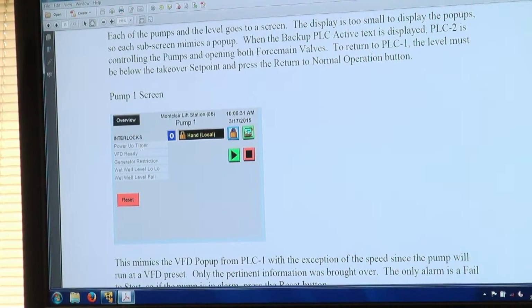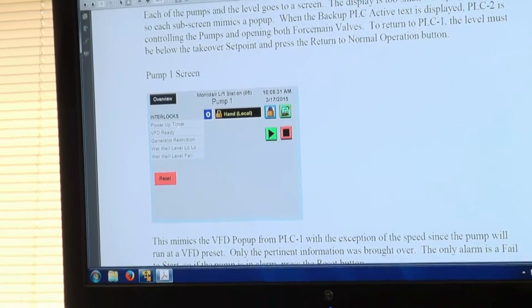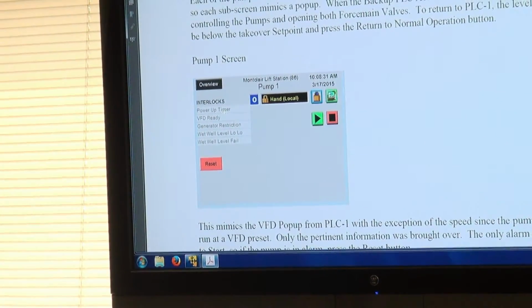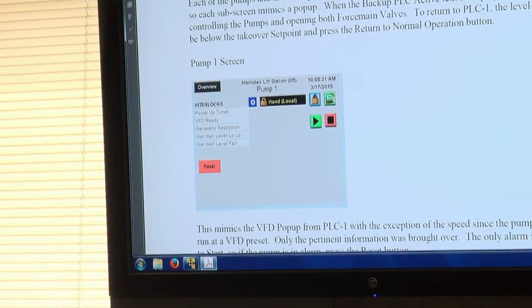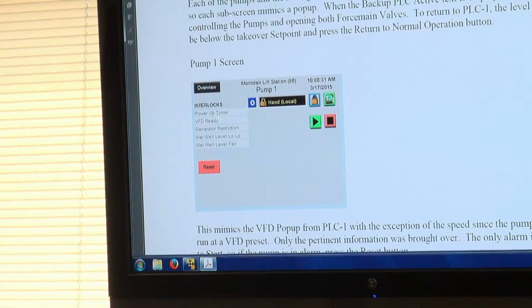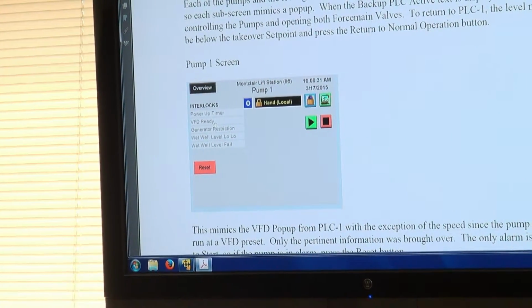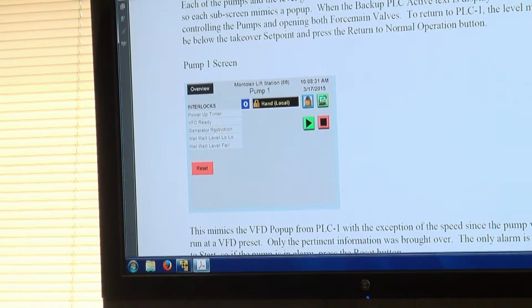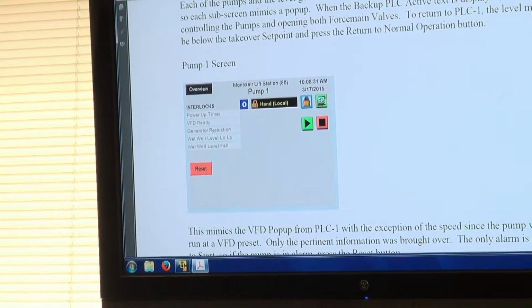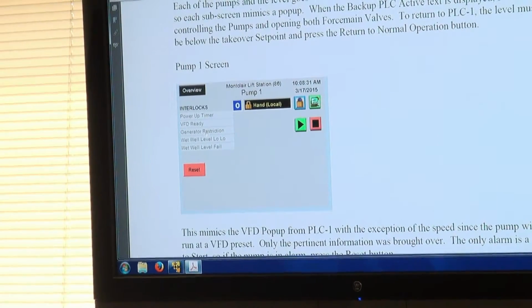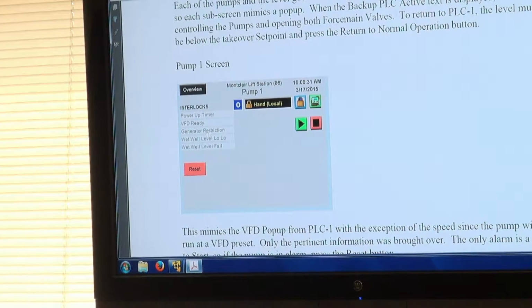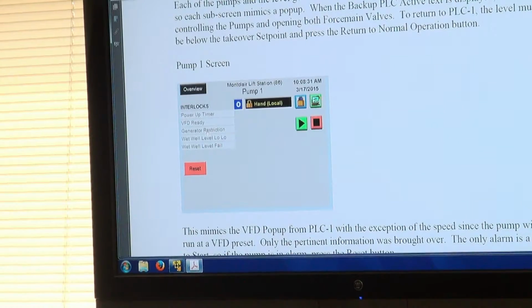We have our power up timer. Basically when a PLC restarts or we switch from emergency to normal or normal to emergency, there's a small delay to make sure that the levels are coming in accurately. We have the ready signal coming in. We have a generator restriction. We talked about that. If 2 pumps are running, it doesn't matter if the VFD's on in hand and running or if it's called from the PLC. If 2 of them are running, the 3rd one will be not ready.